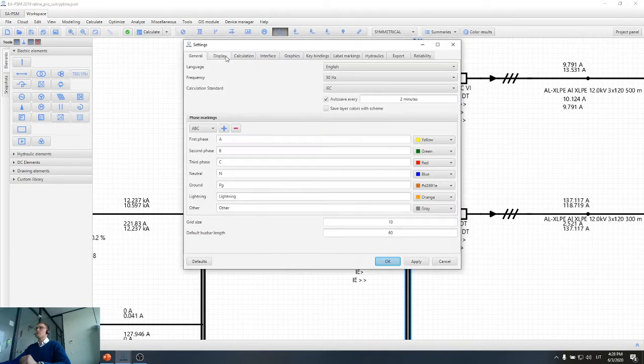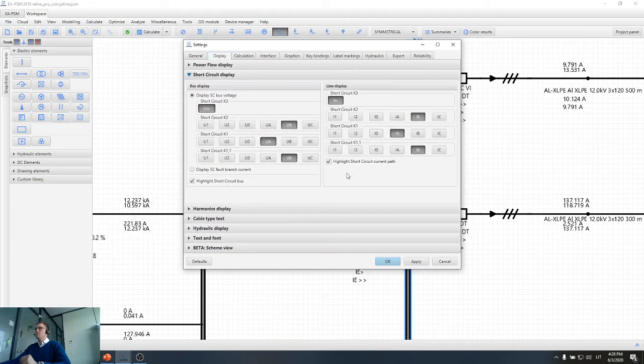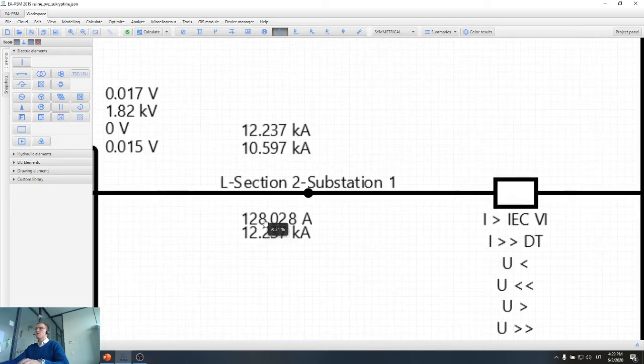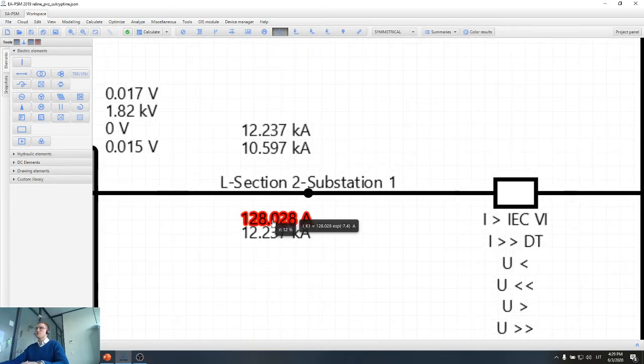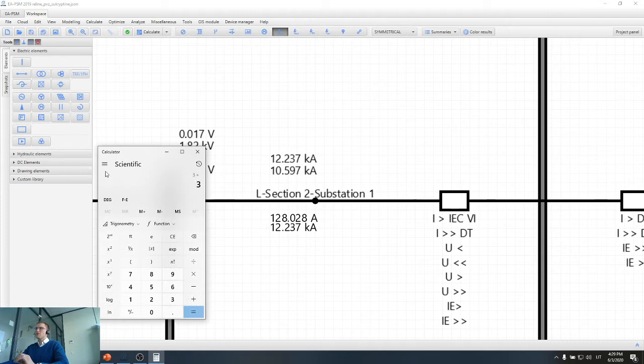So I will go to the display options. The thing is that ground fault protection devices measure zero sequence current, basically 3 times zero sequence current. So in order to set earth fault protection devices correctly, we need to set them according to the zero sequence currents in the network. So I will select for the software to represent zero sequence current. Yeah, so I can see that the currents have changed. Now in case of a 1-phase short circuit, I have a current equal to 128 amps, and this is the zero sequence current. The earth fault protection device measures 3 times zero sequence current, so 384 amps.